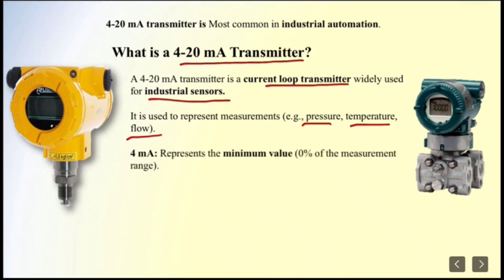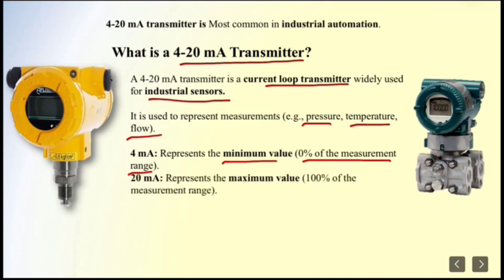In 4 to 20 mA, 4 mA means the minimum value or 0% of the measurement range. And 20 mA means the maximum value or 100% of the measurement range.